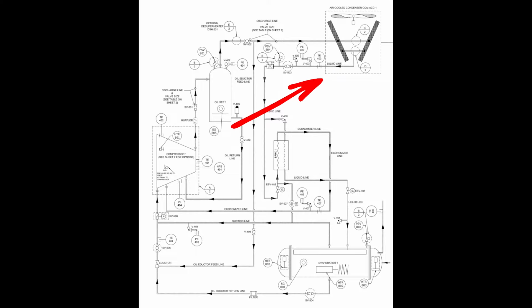Now, this is where this does change. On the Style A, we had an EXV in our liquid line leaving the condenser. We do not have that on the Style B. Okay, so that EXV on the Style A was referred to as the condenser drain valve. But we also had a flash tank, and we don't have that on this machine. We have a brazed plate economizer.